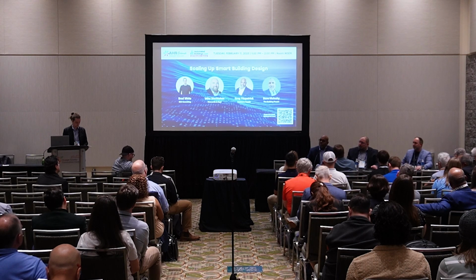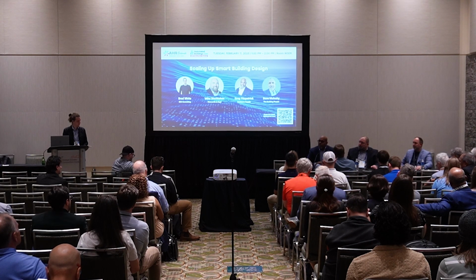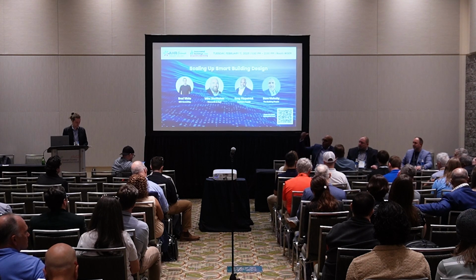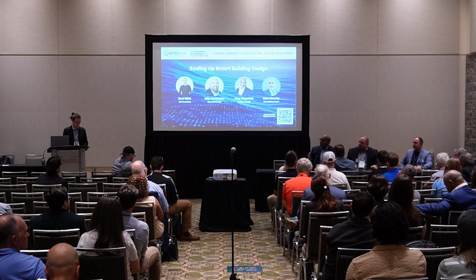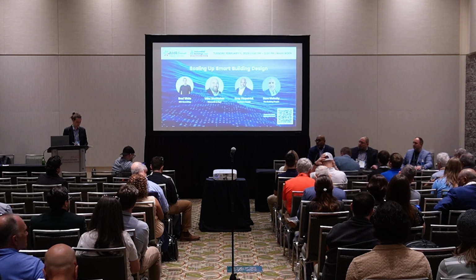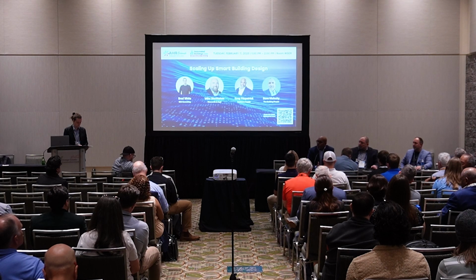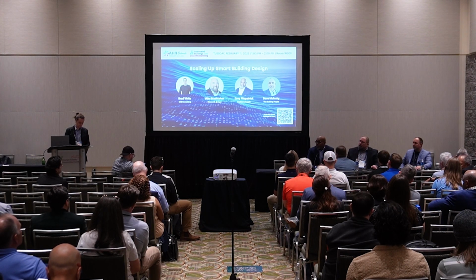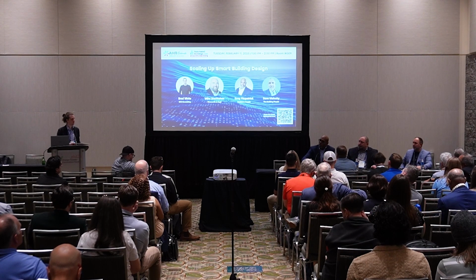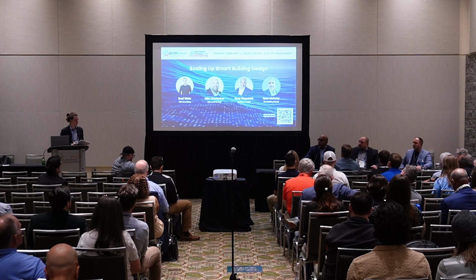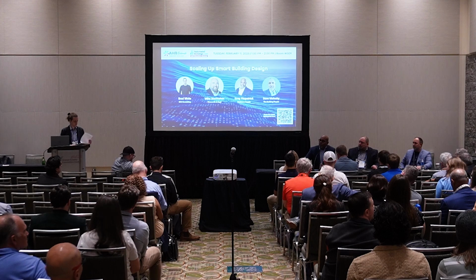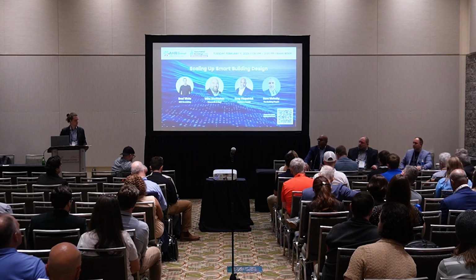Not only that, a systems integration drawing. I'm going to go into that a little later, but we start promoting this drawing called a systems integration drawing that goes from the subnetworks all the way back to, quote unquote, the front end or your web supervisor. How is Niagara being deployed? Is it being deployed in the cloud? Is it on-prem server? Is it being deployed somewhere else? We want to show all of that information on one drawing. You put as much as you can on a set of drawings and the rest in the specification. You don't try to bury things in the specification. You want to put as much on the drawings as possible.